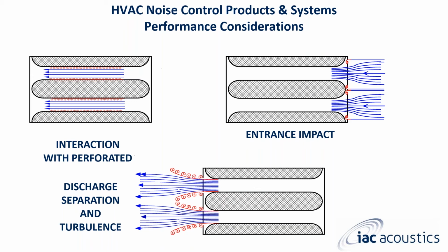With insertion loss, you think, all right, loss is a number in each of the 8 octave bands. The higher the number of the dynamic insertion loss in those 8 octave bands, the more loss you're pulling out of the system. In essence, you're lowering the decibels of the fan or chiller or cooling tower, whatever piece of equipment, so you're making that piece of equipment quieter. You're also making the airflow quieter because you're controlling air movement.